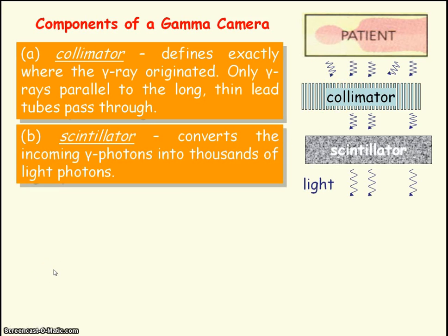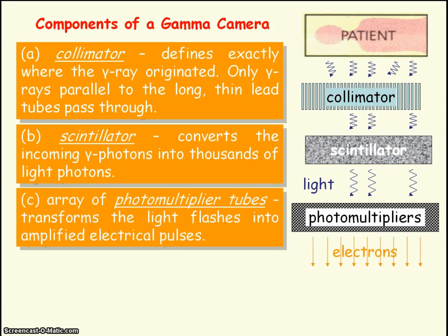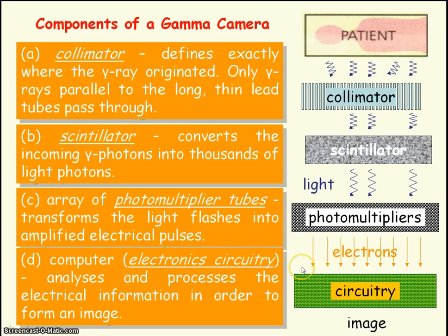The scintillator then converts each gamma photon into thousands of light photons, because the gamma photon has a much greater energy than a visible light photon. The light photons are then sent to a photomultiplier tube, which converts the light into amplified electrical pulses. These electrical pulses are sent to a computer where they are analyzed and processed in order to form the image.